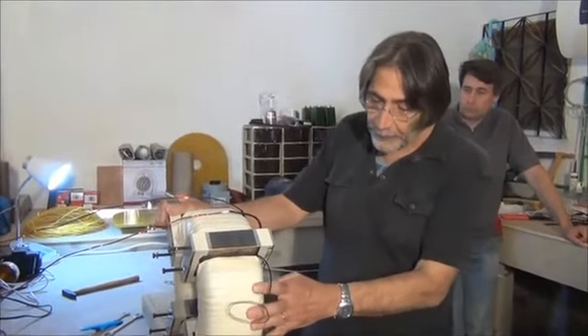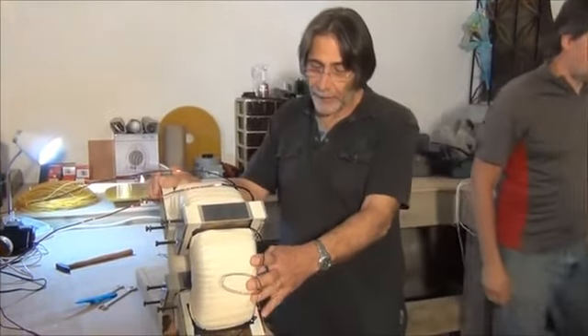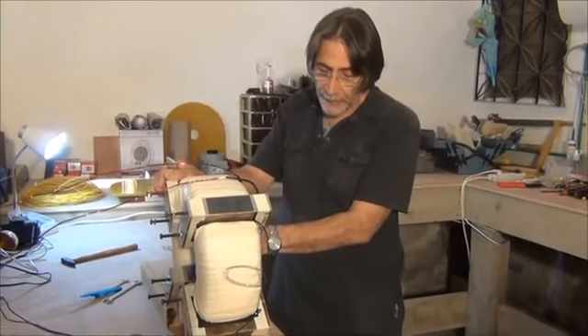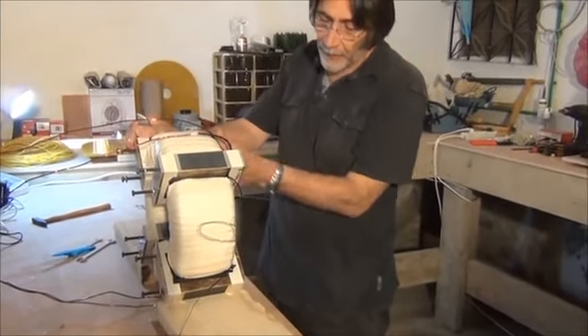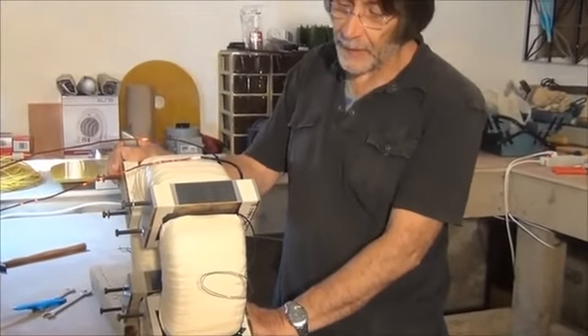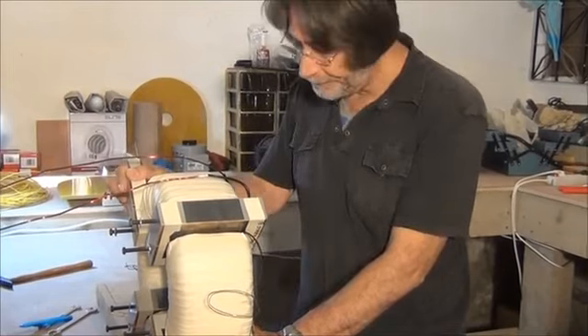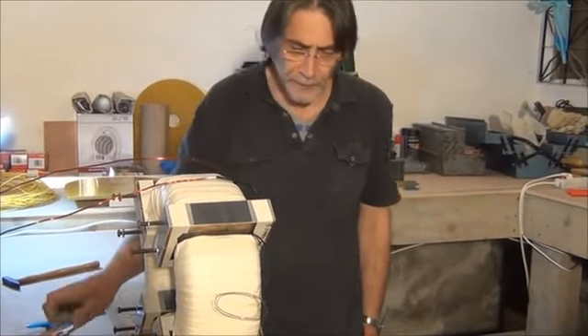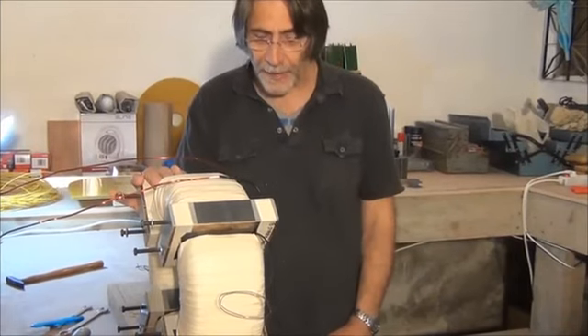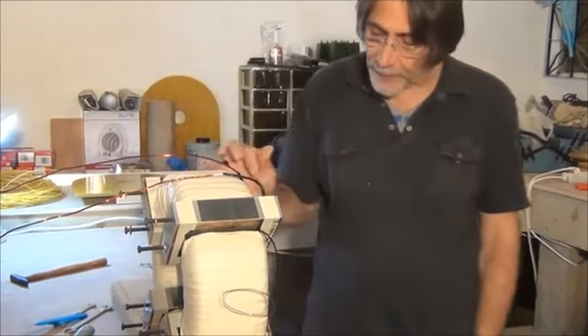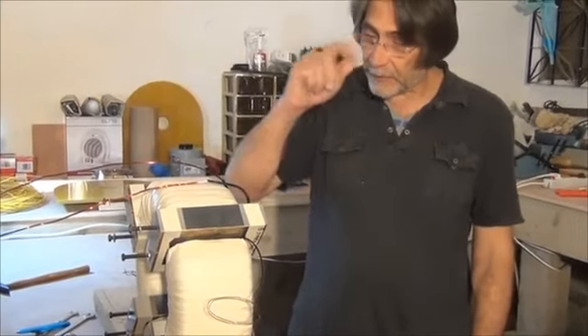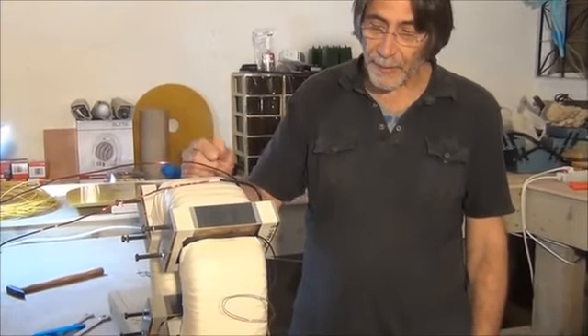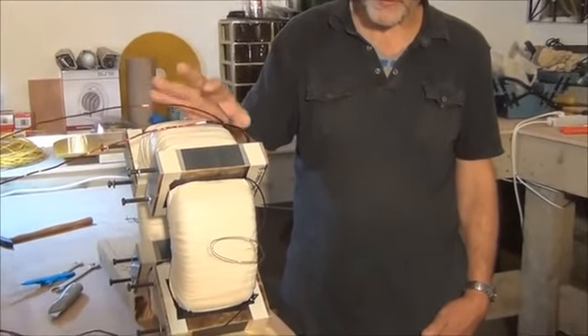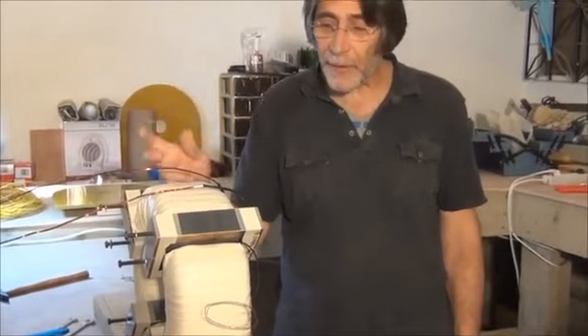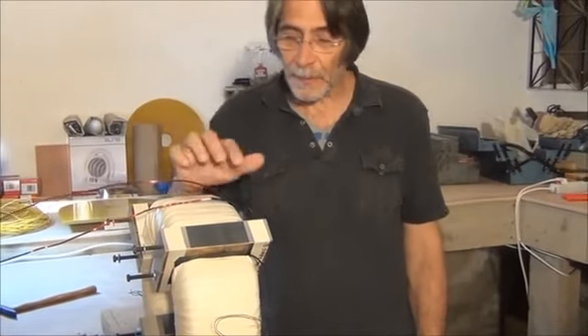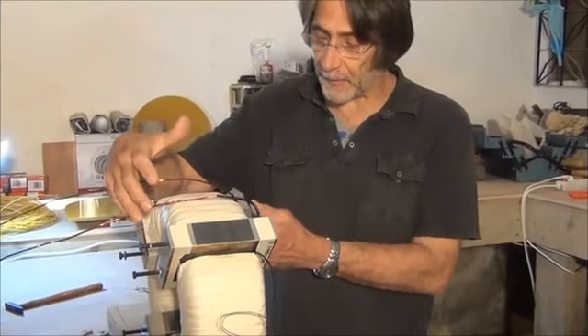We have 3,100 turns of 20 gauge in this winding and this winding. And the output windings are 350 turns of 10 gauge. The new design, we have a new design, well, before I go into that, the way the core is built, we have two layers of mica tape on the bare steel, and then there's a third layer of mylar tape that has a very good cut-through resistance over the mica tape, and that's on the bare steel core.